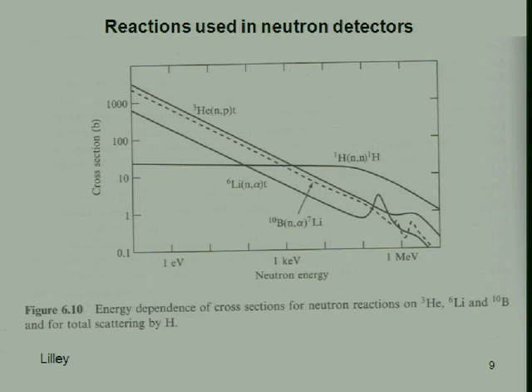It's based on helium-3. So helium-3 is a stable, although rare isotope of helium. You can fill a gas proportional counter with helium-3 gas, and if it gets exposed to neutrons, it turns out the neutrons have a very, very large cross-section. You can see at thermal energies it's thousands of barns, and it falls off like 1 over the velocity of the neutron, as we've seen before, for an n,p reaction. So the neutron gets captured on helium-3. It makes a compound nucleus of helium-4, but in a very highly excited state. And that compound nucleus then falls apart, and it falls apart mainly into a proton and a triton.